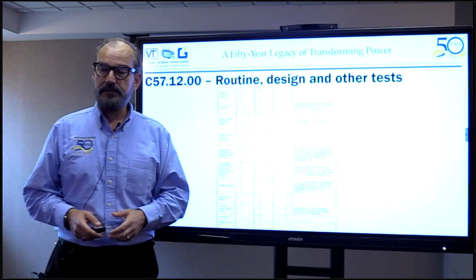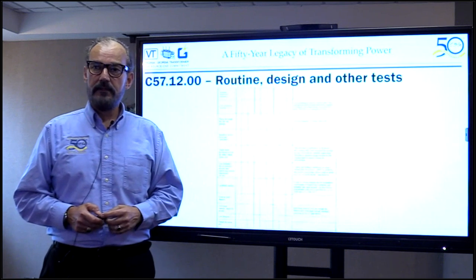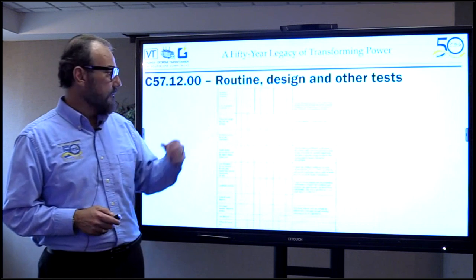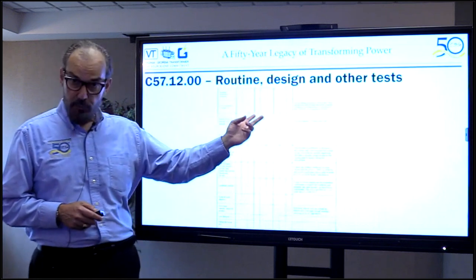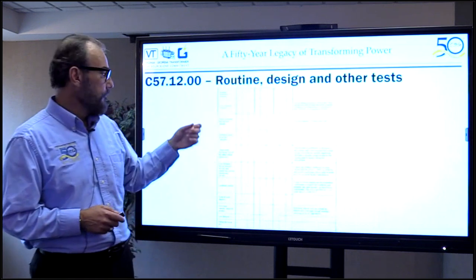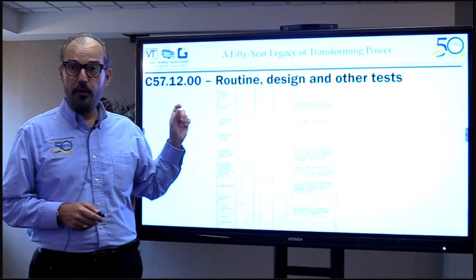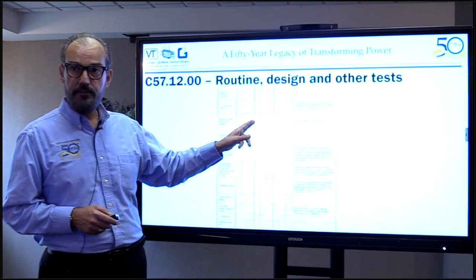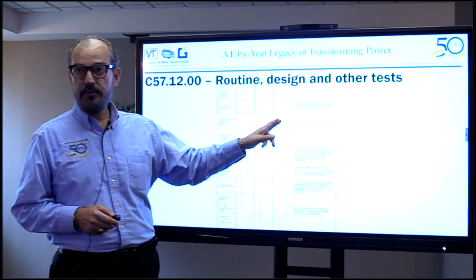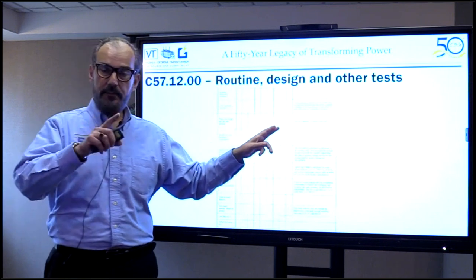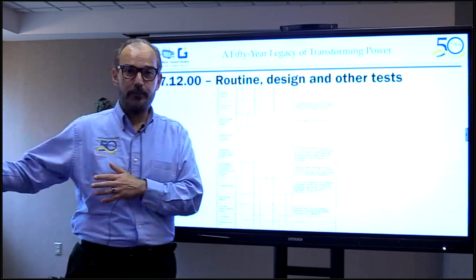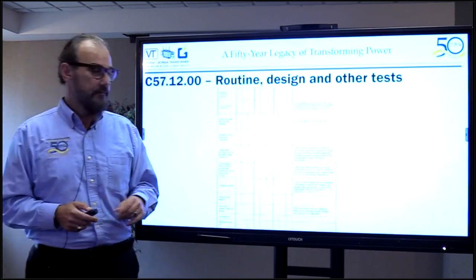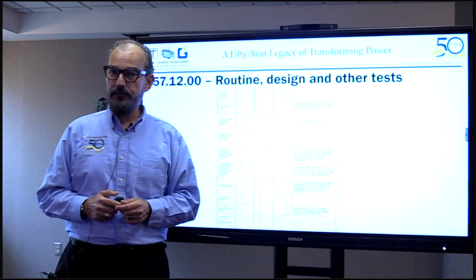Winding insulation resistance — often called a megger test — is a routine test. Core insulation resistance is also routine for class one and class two. Partial discharge test for core gassing is routine for class one but not applicable to class two. Insulation power factor is routine for both class one and class two transformers.